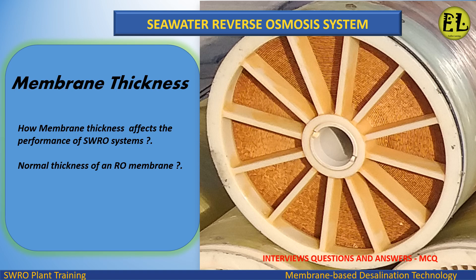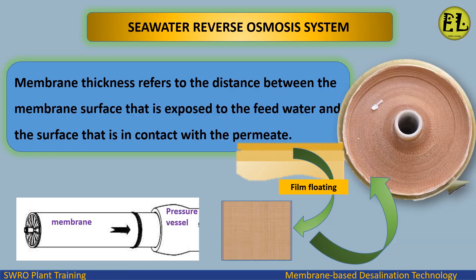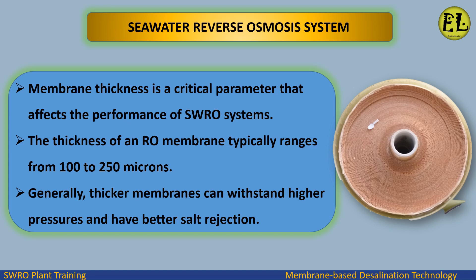Membrane thickness refers to the distance between the membrane surface that is exposed to the feed water and the surface that is in contact with the permeate. Membrane thickness is a critical parameter that affects the performance of SWRO systems. The thickness of an RO membrane typically ranges from 100 to 250 microns.